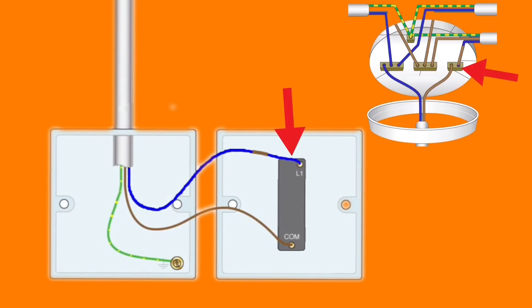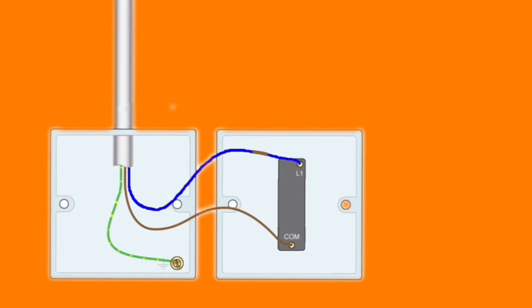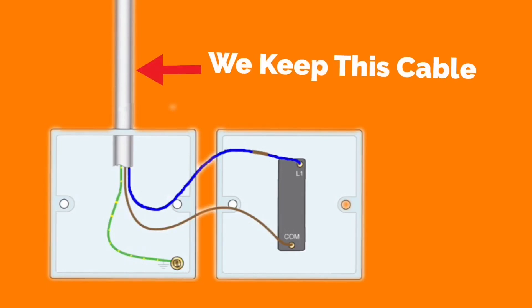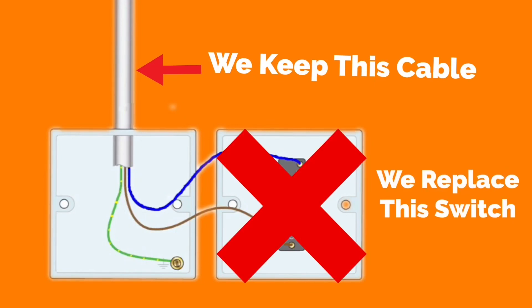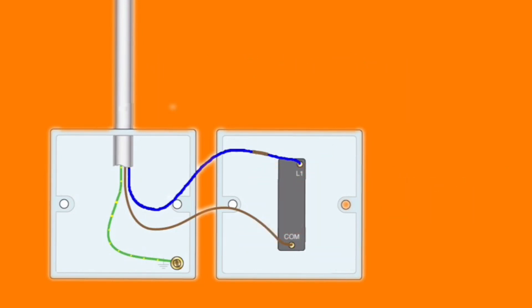Operating the switch puts a switching line conductor through to L1 and turns on the lamp. The switch drop could be in twin brown - in which case both conductors are already identified and no sleeving is required - or in old colors in red and black with the black identified with red sleeving, or in twin red. Whichever of the four variants it is, in this case twin and CPC, the cable remains in place. However, the one-way switch will need to be removed and replaced with a two-way switch at the original position, and a new two-way switch added at the new position.